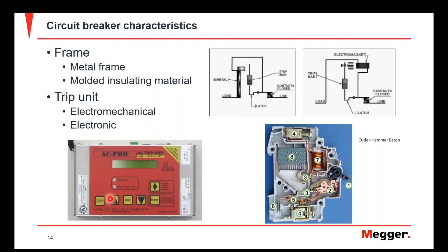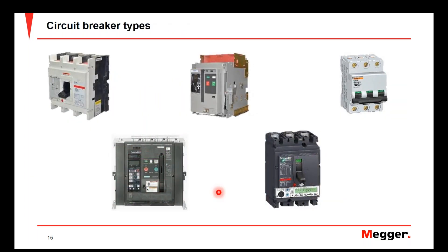For electronic trip units, there will be a set of current sensors mounted to the main conductors of the circuit breaker that communicate signals to the electronic trip unit to allow the breaker to trip. The electronic trip unit outputs to a trip mechanism and opens the breaker. These are some different circuit breaker types we see during primary injection testing — molded-case circuit breakers, metal frame breakers both outfitted with electronic trip units, and miniature breakers you may see in a control power scheme.